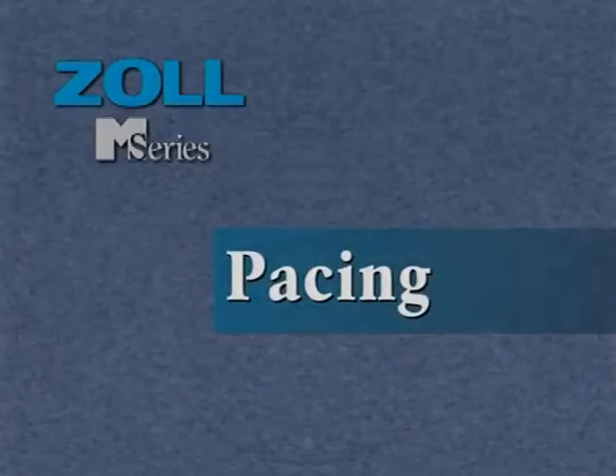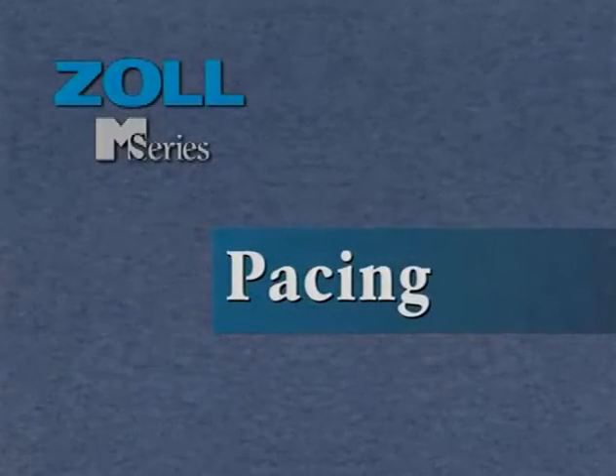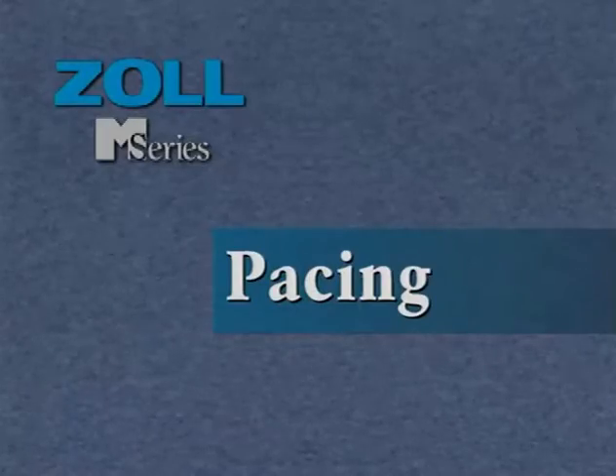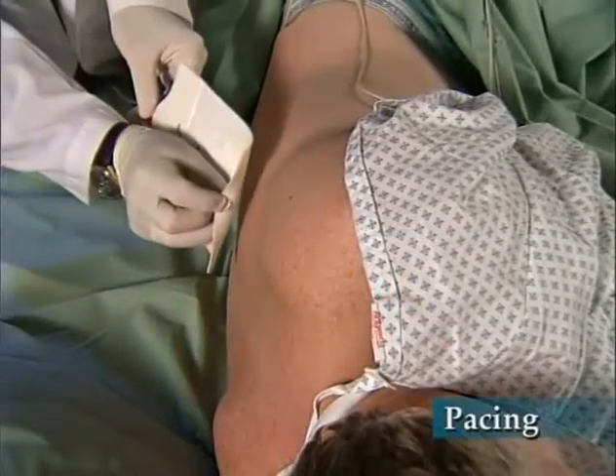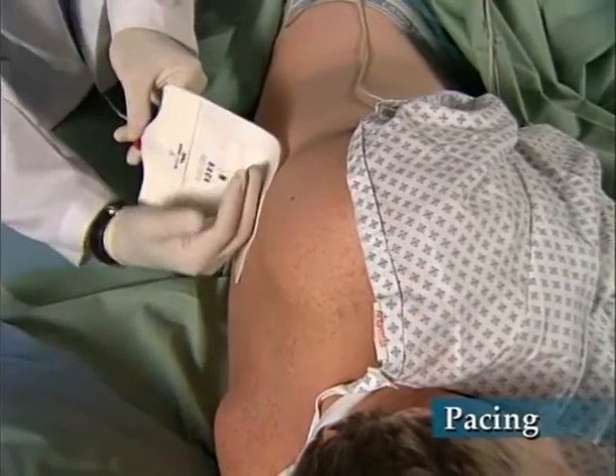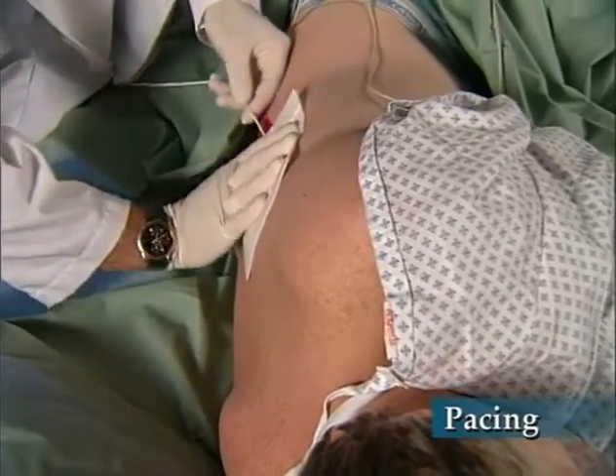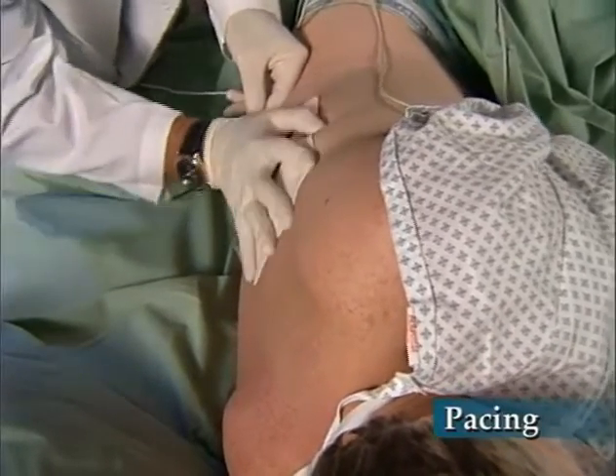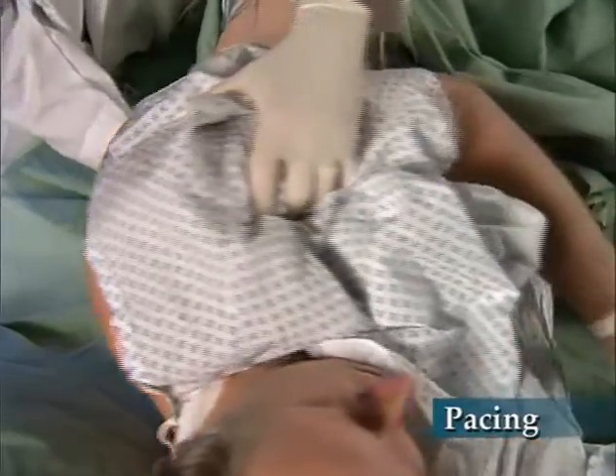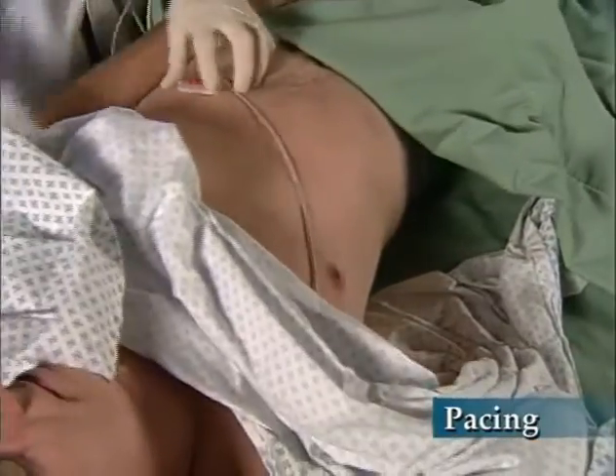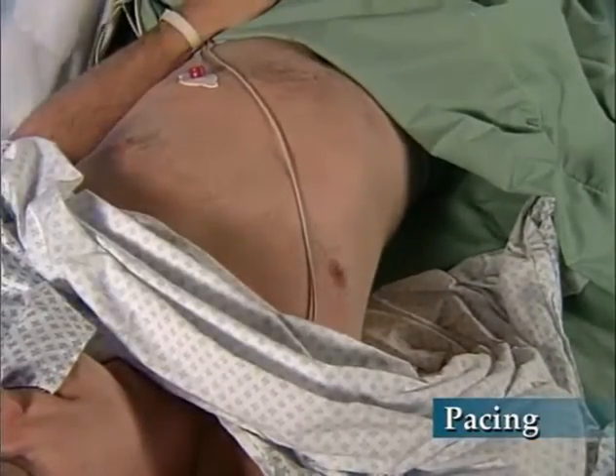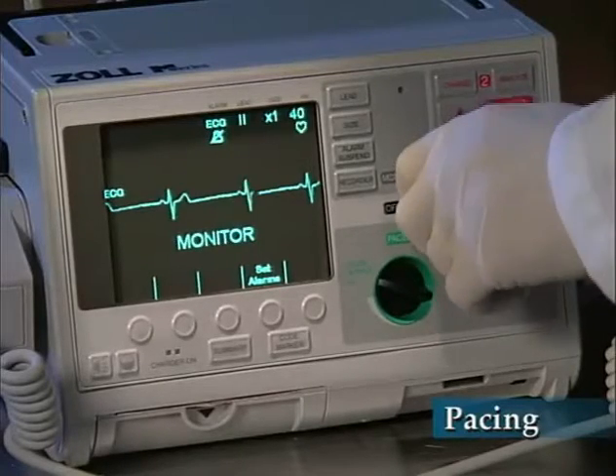This section covers the use of the M Series non-invasive pacing capability. Apply ECG electrodes to the patient as shown previously. Apply the multifunction electrode pads following the directions on the pouch. Pacing is best accomplished with anterior-posterior electrode positioning. Turn the selector switch to Pacer.